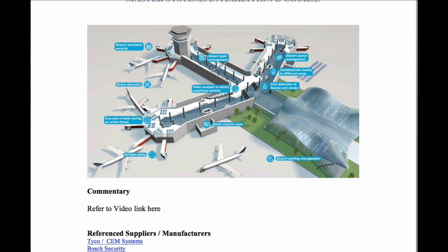If you have a problem over here, you don't want to necessarily tell all these people down here over the PA system that there's a problem. You want to maintain calmness in your airport. You don't want to create a panic where they all start racing towards this area when they don't need to. So that's another area that you need to pay attention to, the zoning associated with access control as it's coordinated with your fire alarm system and perhaps public address system.